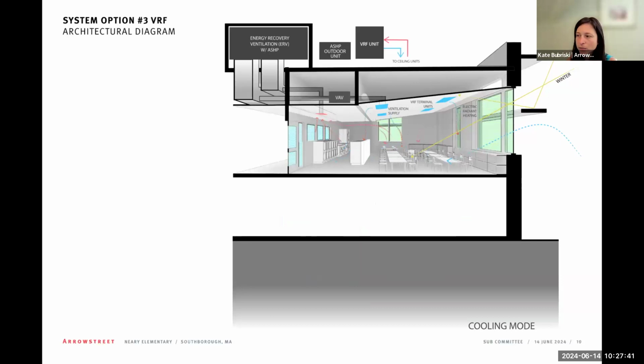The VRF system is going to be all rooftop equipment. Your air handlers, you also have outdoor units for the VRF, and then you'd have fan coils in the ceiling. So this is going to have active fan coils, not just supply grills. And so you have fan coils with motors and filtration and other components that do need to be maintained. And that's probably the biggest difference between this and the ground source systems, is you have a lot more active equipment that needs to be maintained throughout the building.